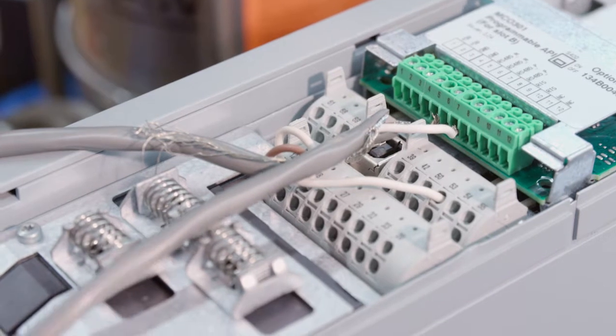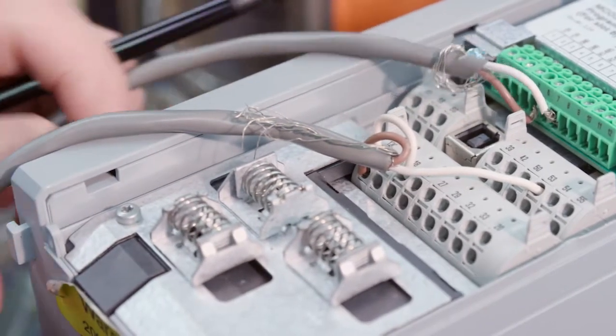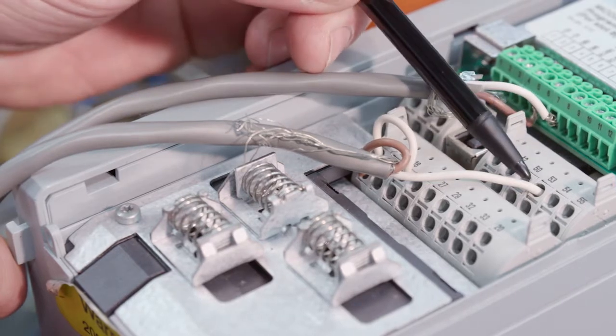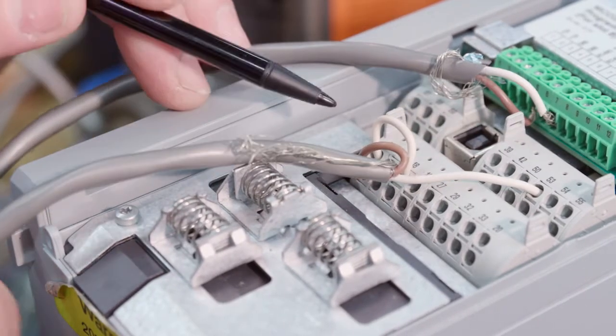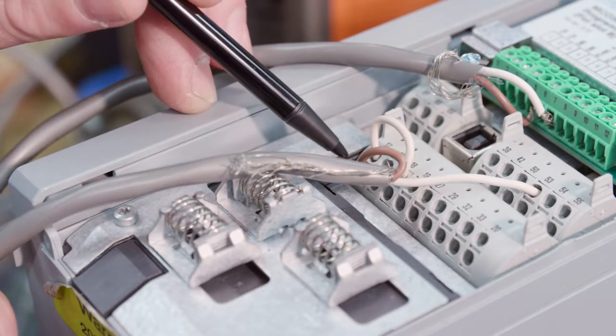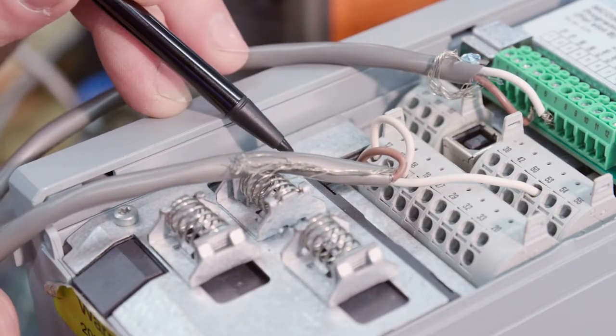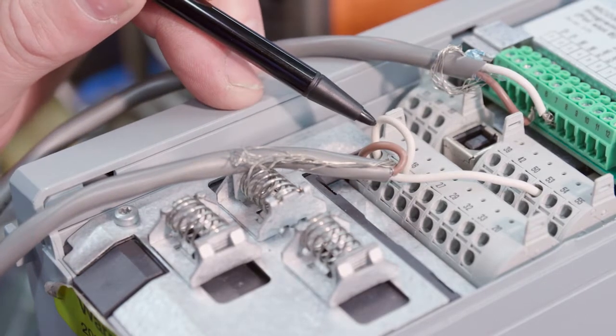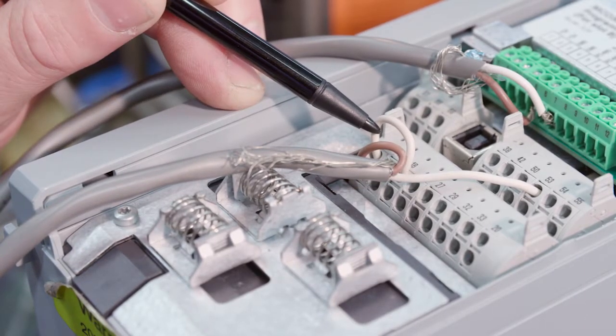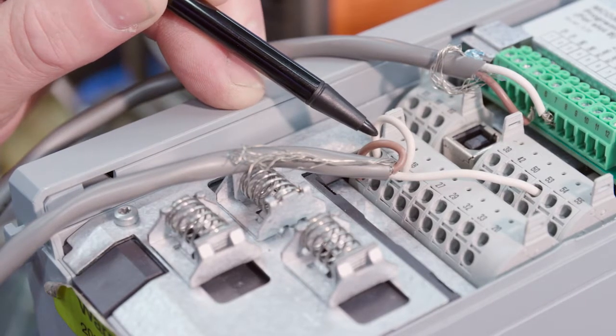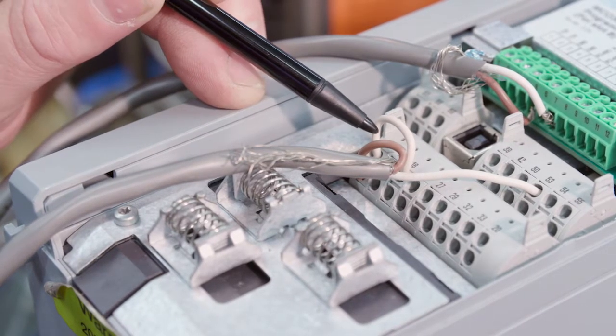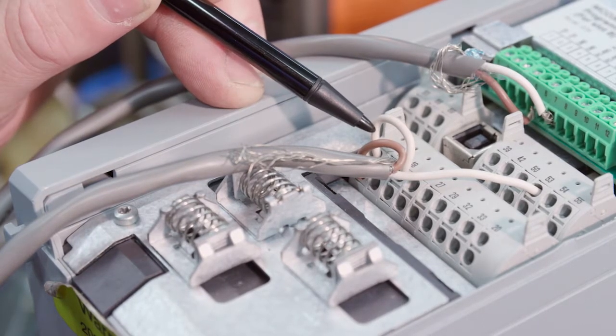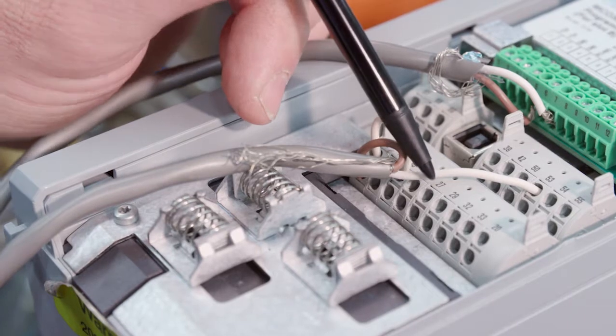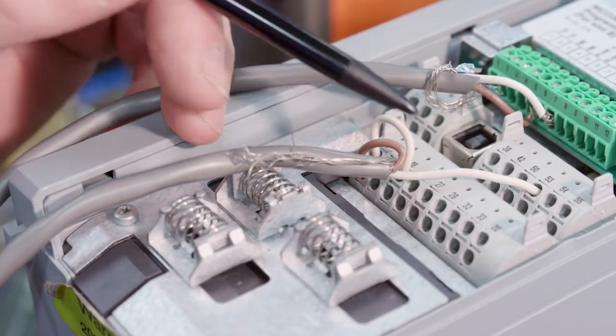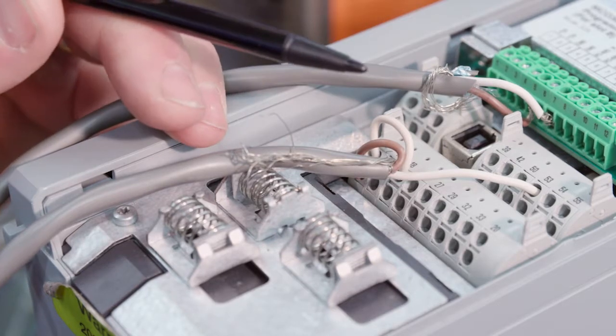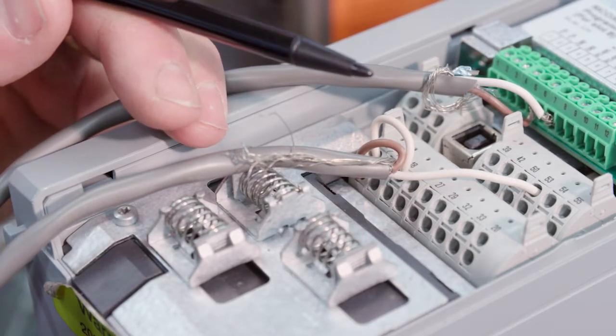Now let's move on to the transducer, and nothing changes here. So we still have white on analog input 53, and we have to power the transducer, and we're getting that from number 12 in this case. Note, we still need our start jumper between 12 and 18. If you are not supplying some other signal, then, just like before, you have to connect a start jumper. Note one jumper that's missing with the advanced platform is the no water loss of prime restart jumper. You do not need that with the advanced platform.